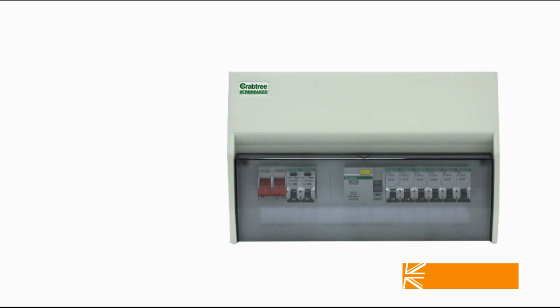There are situations where the use of AFDDs, if mandated, would be pointless, as in a recent example I gave while discussing this on the SGTV channel. Take this consumer unit located in a broom cupboard. Full RCBO and RCD protection, that's nice. The client wants a socket outlet to be mounted adjacent to it for charging their cordless vacuum cleaner. As someone appointed to undertake the work, I have several ways of doing it. I could break into existing socket wiring so that this new point runs from a circuit already present, although I'd have to fully test that circuit in order to certify the work.